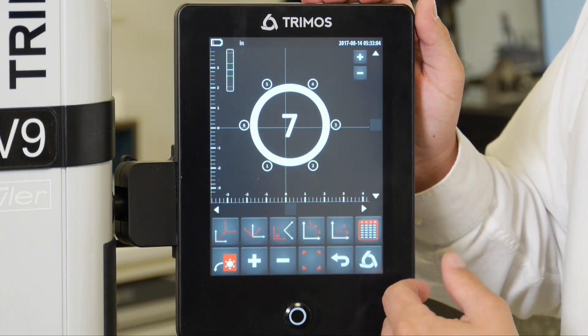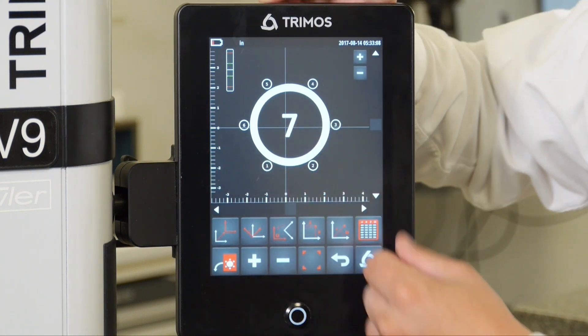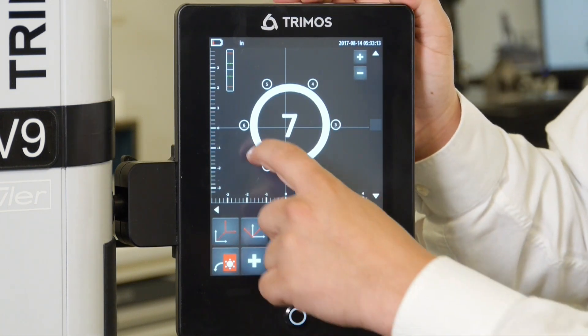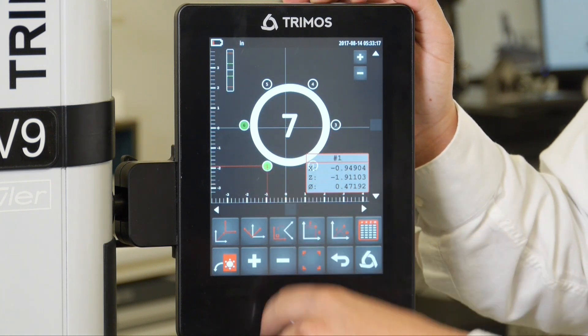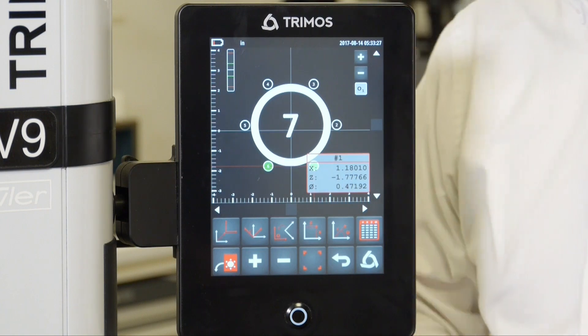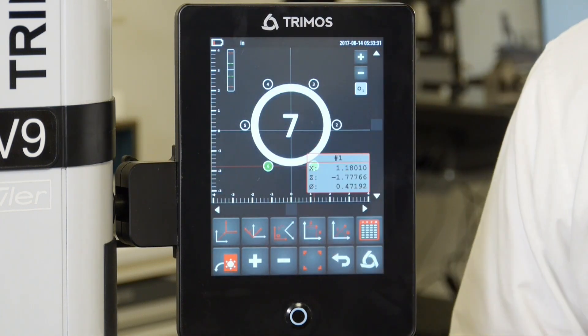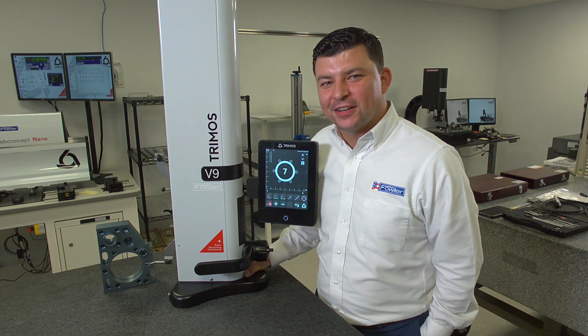If we switch over to more functions, you'll see that I'm aligned currently to bore 1 and bore 2, but if I wanted to reorientate this part, I could do so. If I select bore 6 and bore 1 and hit my orientation button, you'll see that I'm now orientated to bore 1 and bore 6 — basically allowing us to realign the bore on the display as opposed to how we presented it to the part. And those are some of the 2D functions of the Trimos V9 height gauge.